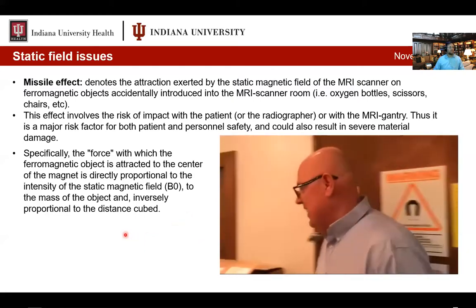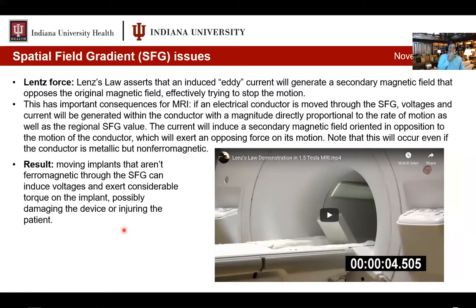Spatial field gradients are due primarily to Lenz's forces. Lenz's law asserts that an induced eddy current, a circular current that forms in a non-ferromagnetic metal, generates a perpendicular secondary magnetic field that opposes the main field. And that effectively stops the motion. So if you're moving a piece of aluminum into the field, the spatial gradient will create Lenz's forces in that object that create eddy currents, which look like eddies in the water. They're electrons flowing in circles.